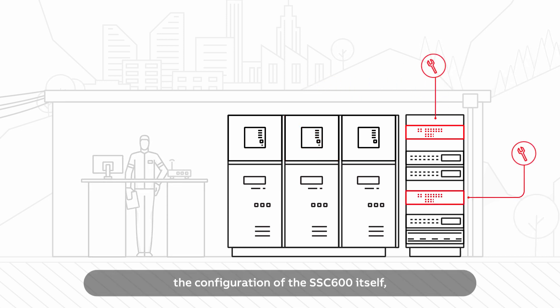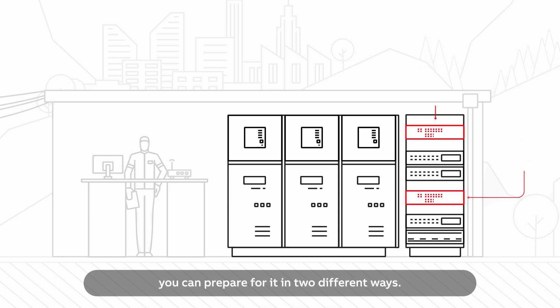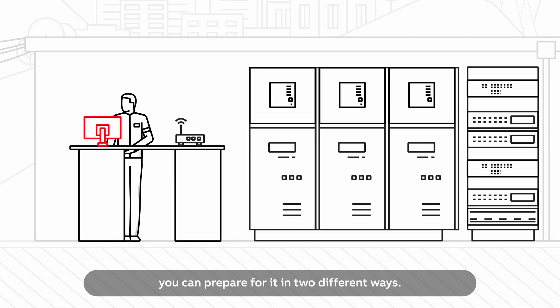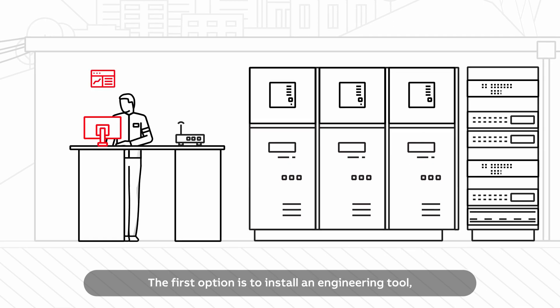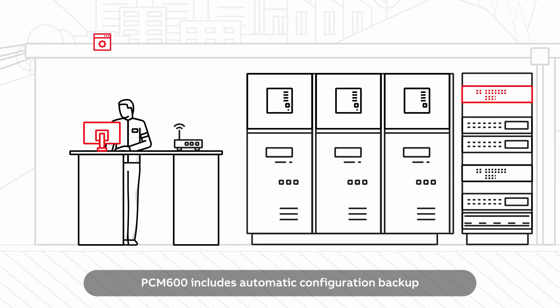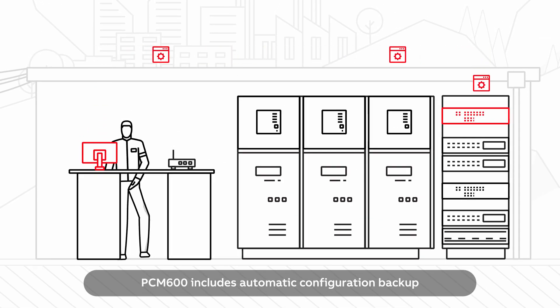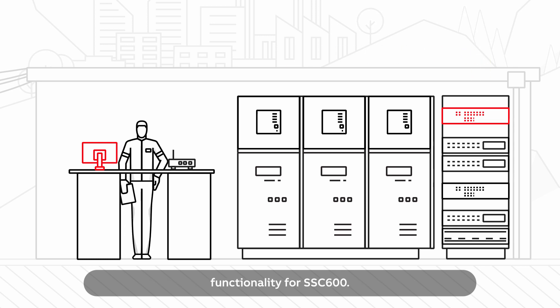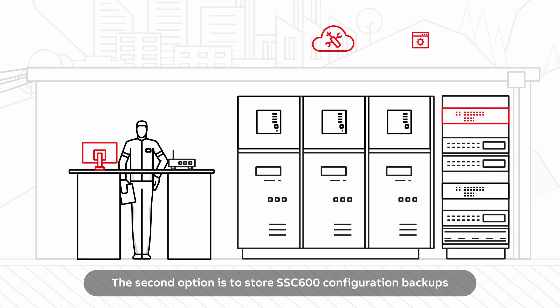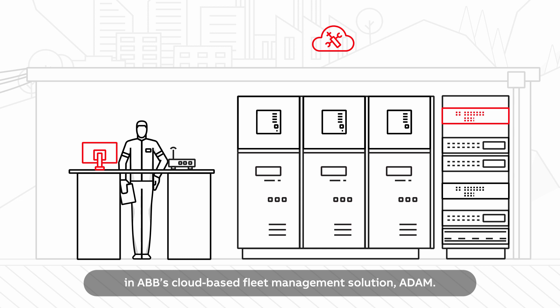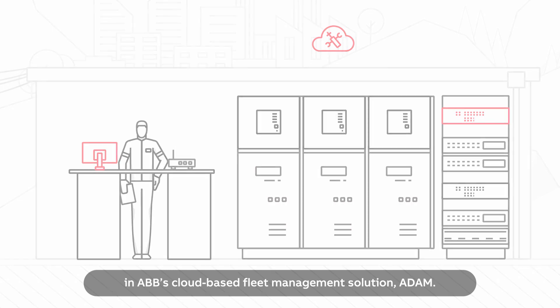In case there is a need to restore the configuration of the SSC600 itself, you can prepare for it in two different ways. The first option is to install an engineering tool such as ABB's PCM600 on the substation computer. PCM600 includes automatic configuration backup functionality for SSC600. The second option is to store SSC600 configuration backups in ABB's cloud-based fleet management solution, ADAM.